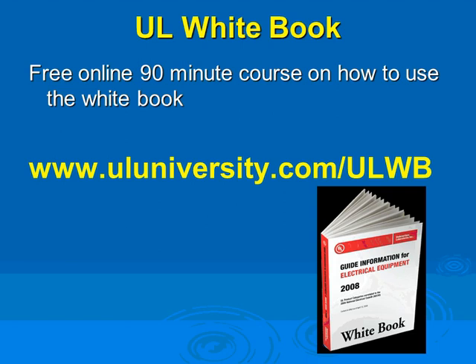So for example, I'm picking resistors and reactors. The UL product category code for resistors and reactors, which is Article 470.1 in the NEC code book, is NMTR, and they give you a table and a page number where in this book you can find this and read more about it. So what I'm trying to get to is they make it very, very easy.